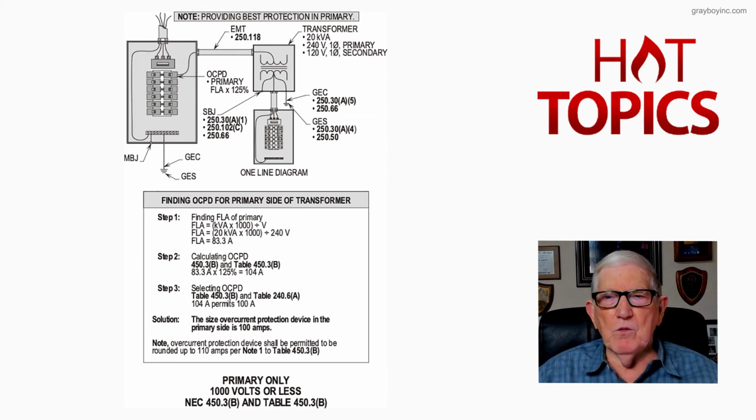The rule of thumb method we always used in the field would be the peak current is equal to 1.414 times the 240 volt single phase primary divided by 0.45 ohms, your transformer winding resistance, and we'd come up with 754 amps.